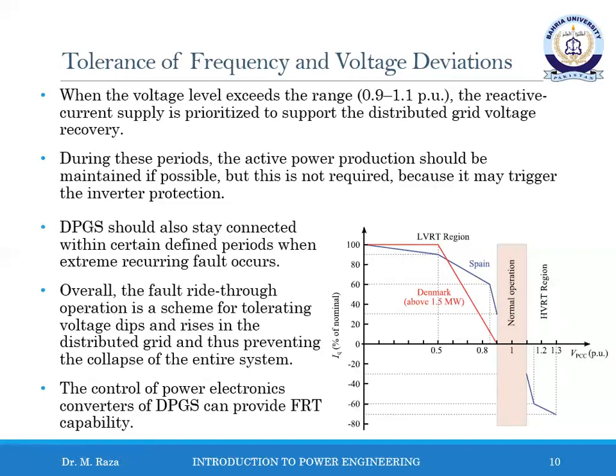Similarly, the red curve represents the Danish grid codes, which state that the 100% reactive current must be injected. Here, the injection means the capacitive reactive current, in case the grid voltage reaches 0.5 per unit. Often, the grid codes provide the guideline when the grid voltage rises, such as these regions. According to Spanish grid code, the distribution power generation system must inject inductive current when the grid voltage rises above 1.1 per unit.